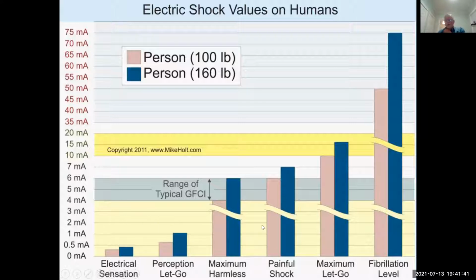But with a ground fault circuit interrupter, if you have a fault and you're part of the circuit, you're going to feel a tingle. But the idea is it trips out the supply before it can do any damage and get into this maximum let-go level or the fibrillation level, which will do you in.